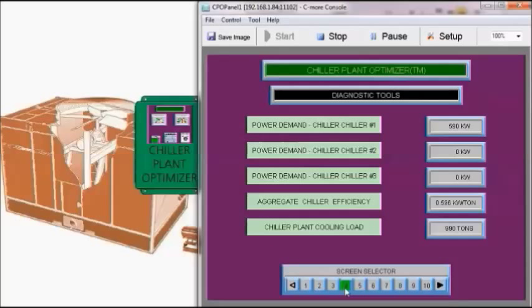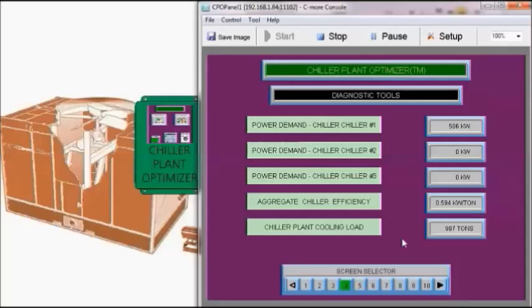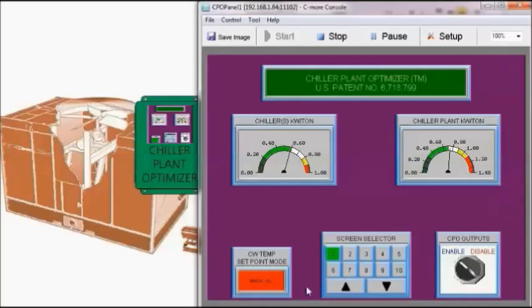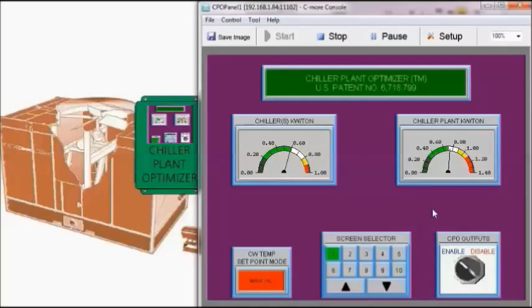Now we can look at our power demand for the chiller 588 kilowatts. Our chiller efficiency at 0.594 kW per ton and we're actually recording a load of 987 tons. We can also look at the first screen and we can see the kW per ton for the chiller and our chiller plant kW per ton which is operating about 0.74 kW per ton.